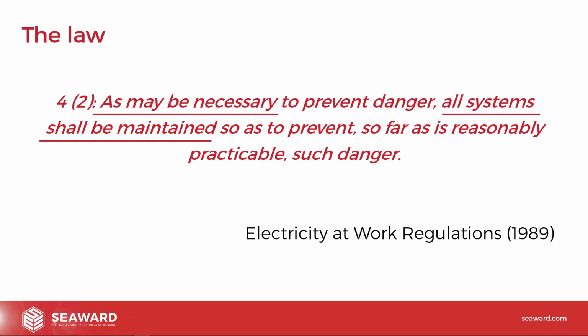Well, as may be necessary to prevent danger. There's nothing in here that says we have to do PAT testing every 12 months. We've got to do it enough to prevent danger. So if we've got high risk equipment in a high risk environment, like a grinder on a building site, we'd expect to do that more often, usually in this case 3 months. And if we've got low risk equipment in a low risk environment, like a PC in an office, chances are we probably would do that less often, maybe say 3 years.